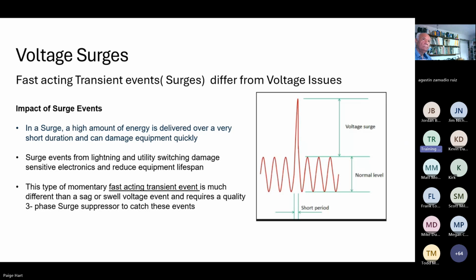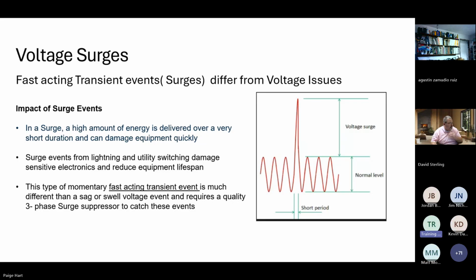Now, voltage surges are another thing that we're seeing more and more of these days, these fast-acting transient events that differ far from the normal voltage anomalies we were talking about before. A surge, unlike the voltage issues we were just discussing, is a very high amount of energy delivered over a very short duration. This type of voltage spike or surge can really quickly damage equipment that has sensitive electronics in it. Most of your three-phase equipment, a lot of your commercial equipment, almost everything these days has electronic devices in it doing some type of control in the circuit, and if you get surges in there, they're going to take out those electronic controls very quickly.